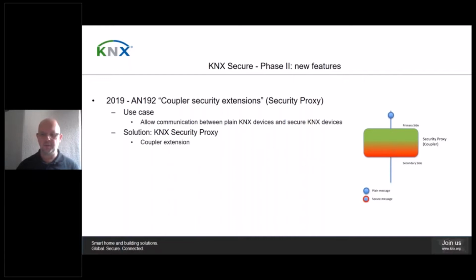It makes no sense that the plain and the secure communication is on the same subnetwork, so the coupler is the logic place where to do such translation. This can be in a TP1 coupler, the TP1 RF media coupler, or in the KNX IP router. The security proxy works bidirectional. It translates between plain and secure multicast group communication in both directions and transparently. It works only for group communication. Translation of system broadcast communication and point-to-point communication is not foreseen.